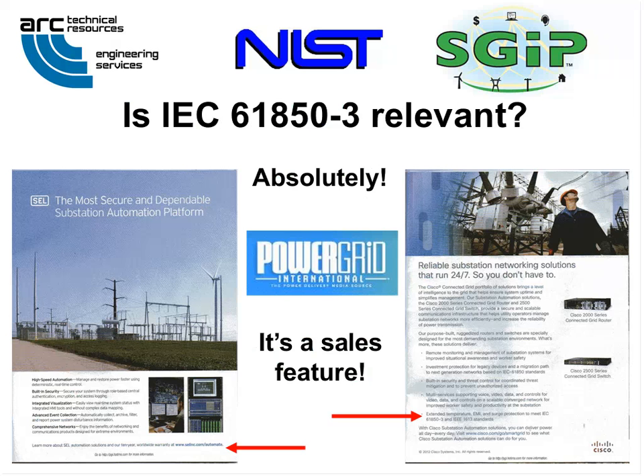Is IEC 61850-3 relevant for this work? Absolutely. Recent advertisements in Power Grid International magazine indicate it's a sales feature. The SEL ad on the left touts that their communications products are hardened to meet stringent IEEE and IEC tests for harsh environments, unquote. The Cisco ad on the right notes that their ruggedized routers and switches already comply with 61850-3 and IEEE 1613 standards. It notes that the, quote, next generation networks will be based on 61850 standards as investment protection. So we felt that since industry was already doing this, we would codify that. In effect, we were catching up with what was already the reality on the ground, which is that American utility communications equipment providers were already doing this.